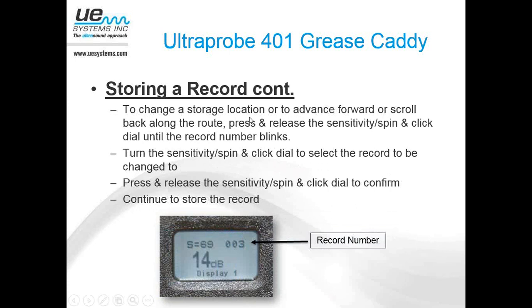Now, if we need to change a storage location, so let's say we've got our route loaded into it, and we get to a particular piece of equipment that we need to collect data on, but that piece of equipment is not running, it's not in service. So we really don't need to collect any data on that. Using that sensitivity spin and click dial, I just keep pressing and releasing that in, and eventually the record number is going to blink or flash. When we see that record number blinking or flashing, using that sensitivity spin and click dial, we can then advance forward and skip over those points. And then we can move on to the next asset where we need to go out and collect the data. And so we've skipped over the points on that piece of equipment that wasn't running.